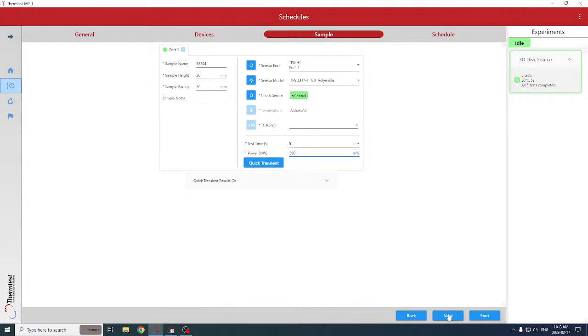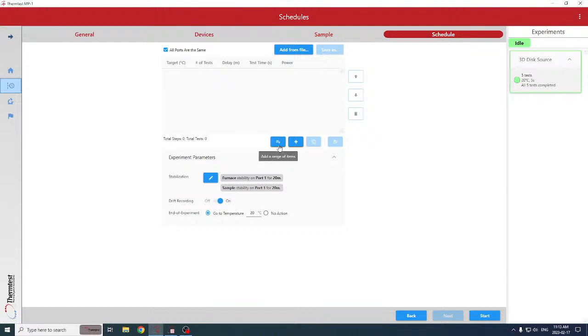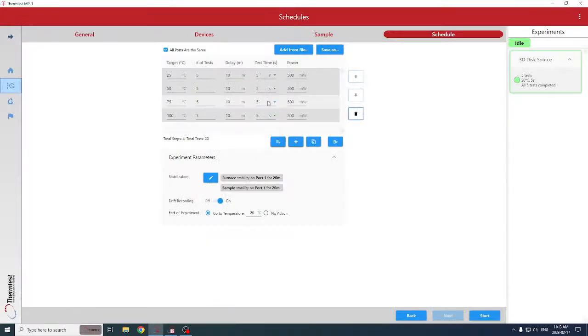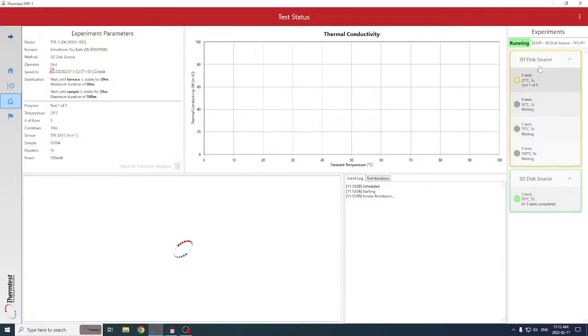We could run a quick transient, but let's go ahead and set up a schedule based off of this confirmed experiment. So here, we could run a single test, which would be go to 50 degrees and make the measurement, but more convenient if you have temperature would be to set up a range of temperatures. So let's go from 25 to 100 in 25 degree increments. We'll use one power of 500 milliwatts and 5 seconds. So we're going to run 5 measurements with a 10-minute delay between each. So it auto-builds our experiment schedule. When we click start, it will automatically start the process of changing the temperature on the schedule, on the device rather, and start the experimental process.